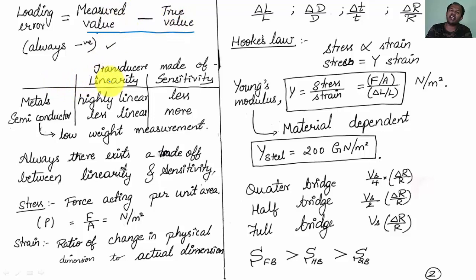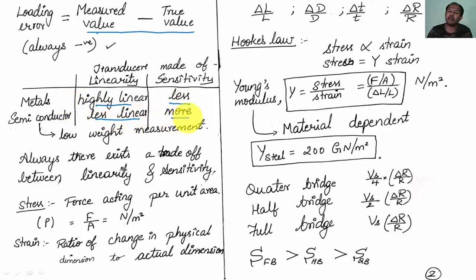These two things are very important. If you are designing a transducer, you can use a metal or a semiconductor. If you use a metal, you can achieve high linearity but sensitivity will be less. If you use a semiconductor transducer, linearity will be less but sensitivity will be more. So there always exists a trade-off between linearity and sensitivity. For heavy weight measurement, we use a metal transducer; for low weight measurement, we use a semiconductor transducer — for example, measuring gold.